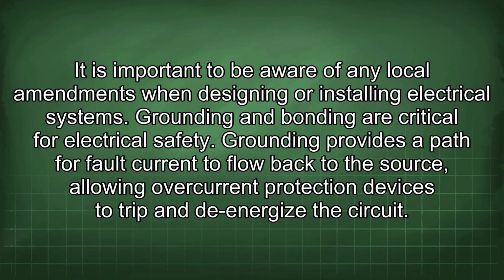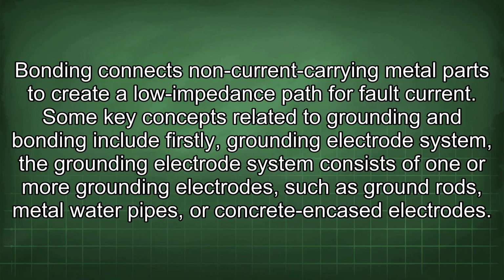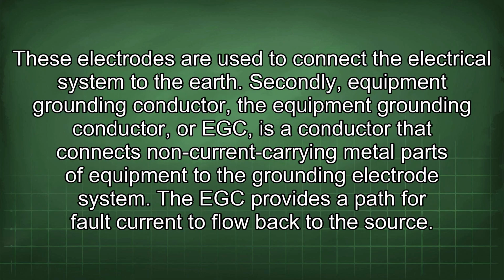Grounding provides a path for fault current to flow back to the source, allowing overcurrent protection devices to trip and de-energize the circuit. Bonding connects non-current carrying metal parts to create a low impedance path for fault current. Some key concepts related to grounding and bonding include: firstly, grounding electrode system. The grounding electrode system consists of one or more grounding electrodes, such as ground rods, metal water pipes, or concrete encased electrodes. These electrodes are used to connect the electrical system to the earth. Secondly, equipment grounding conductor. The equipment grounding conductor, or EGC, is a conductor that connects non-current carrying metal parts of equipment to the grounding electrode system.